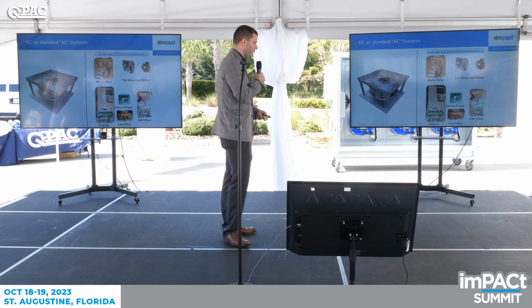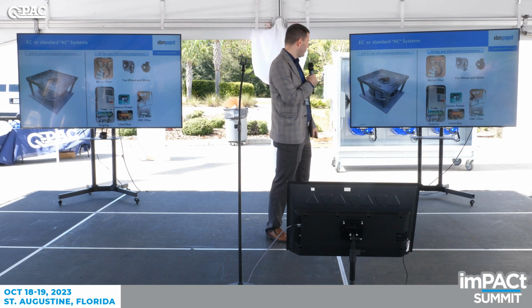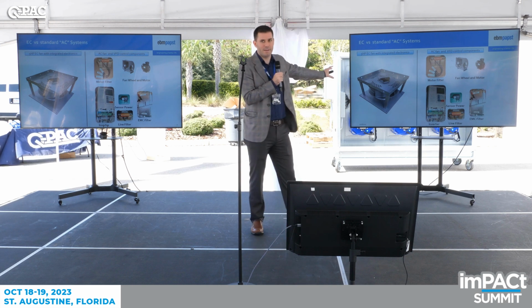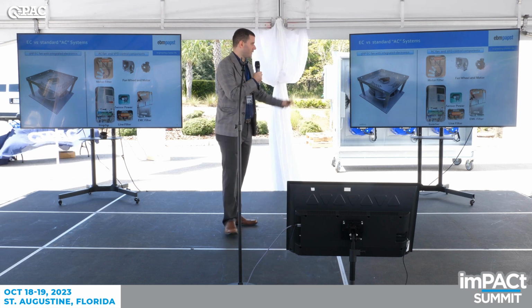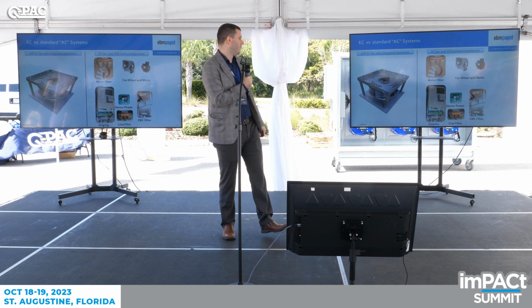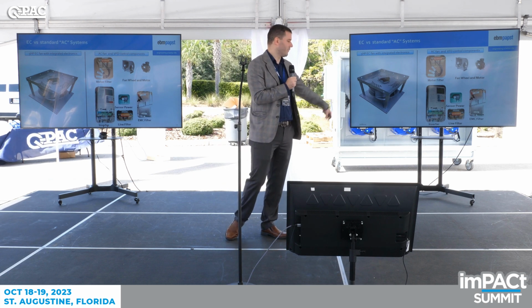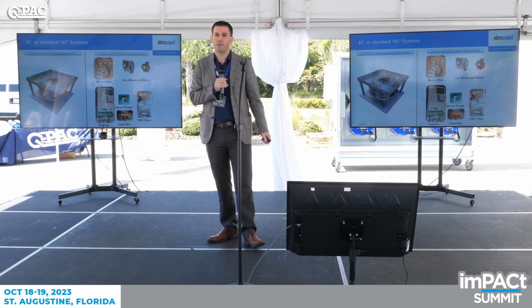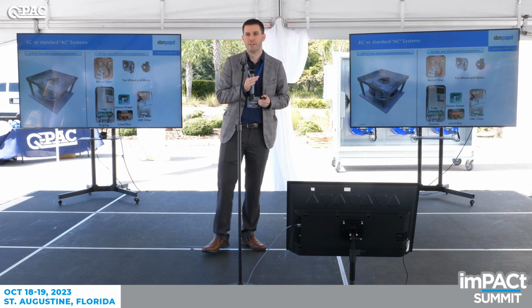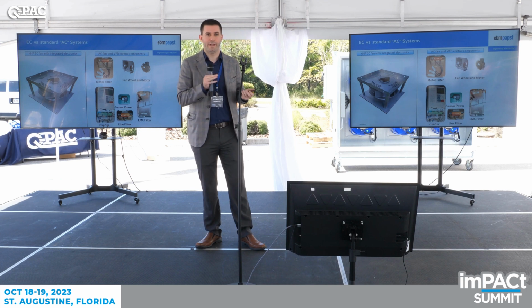So just to show a visual of what's included within the EC fan assembly, you have the motor filters, you have the fan and wheel and motor, you have the VFD, inverter, line filters, EMC filters. All of that's in the EC motor package. So this is saving you weight and room in your air handler.